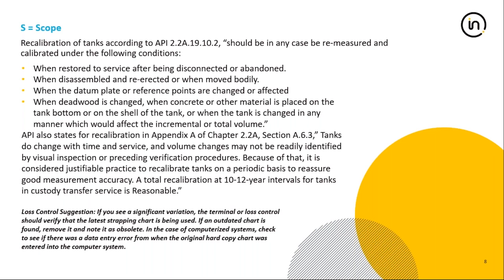The outcome of those inspections is going to tell you whether you need to do a recalibration right now, or you can wait another 5 years and do it on the 10 to 12 year cycle.